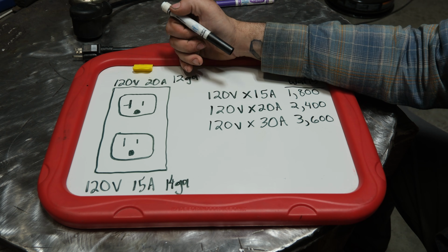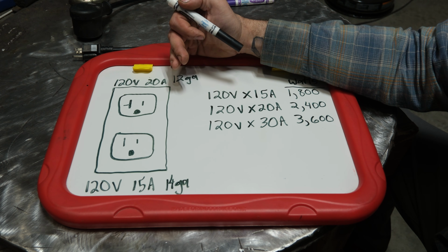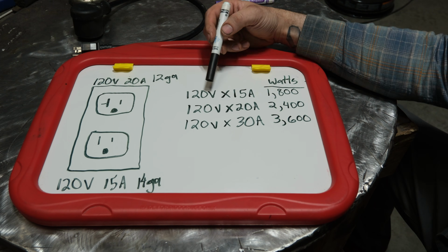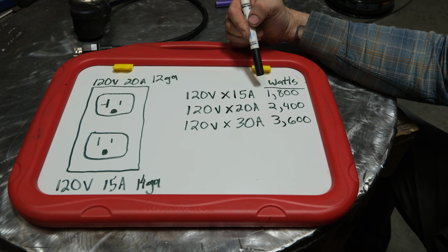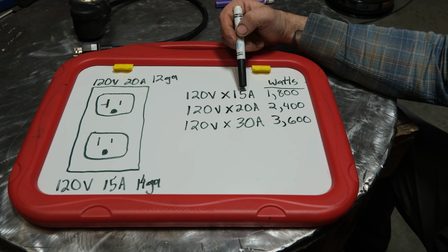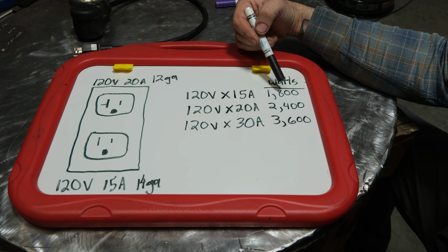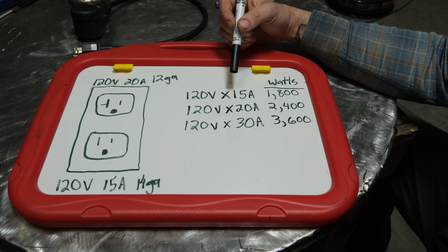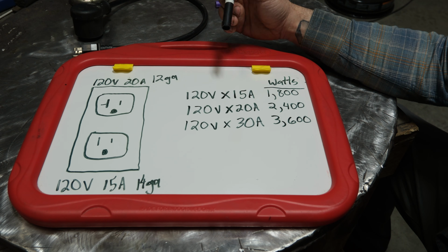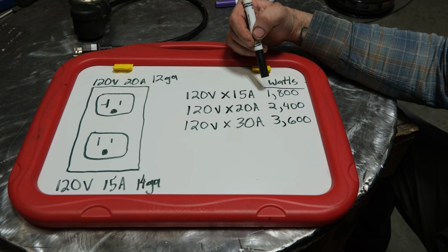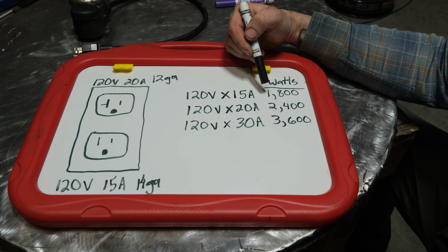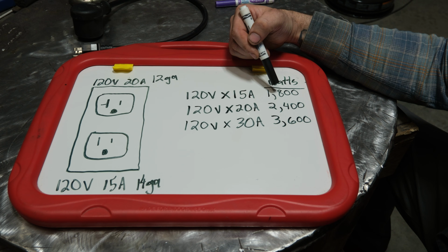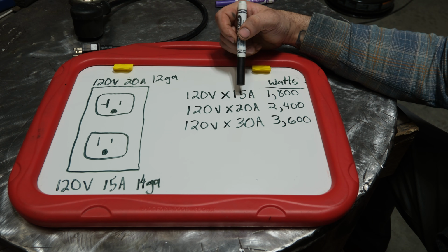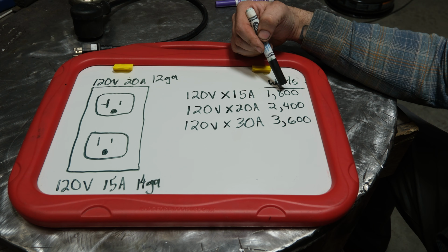Now let's look at some hard numbers of the battle that we're up against dealing with this. These are simple math problems. We are calculating how much wattage is available. On face value, a 15 amp breaker will only allow approximately 1,800 watts of power through it before the breaker trips. Now, the reality is that's not that simple. Breakers will all allow quite a significant overload for quite a significant amount of time before they trip. So 15 amp breaker, this is face value.